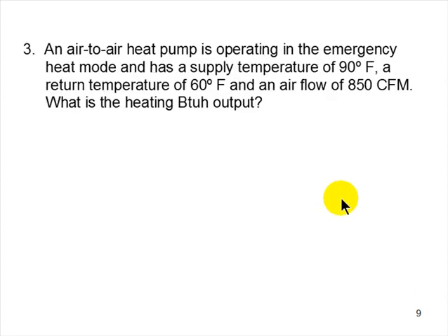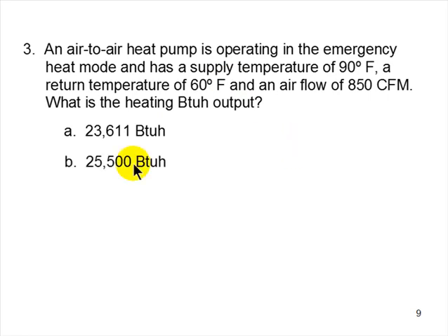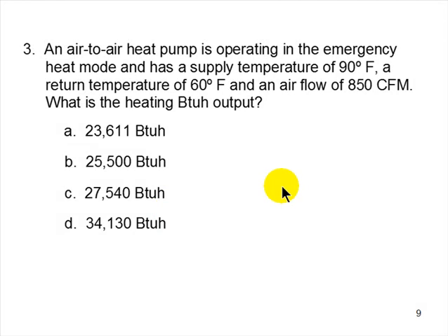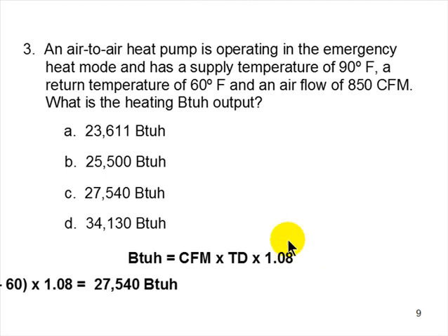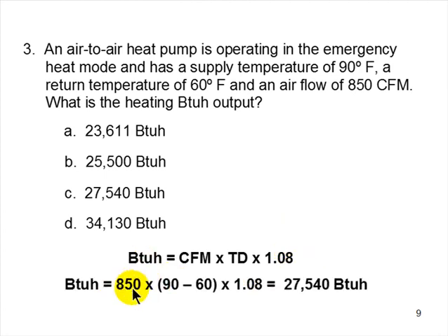Question 3: An air-to-air heat pump is operating in emergency heat mode with a supply temperature of 90°F, return temperature of 60°F, and airflow of 850 CFM. What is the heating BTU output? Use: BTU = CFM × ΔT × 1.08 = 850 × 30 × 1.08 = 27,540 BTU. Answer: 27,540 BTUs.